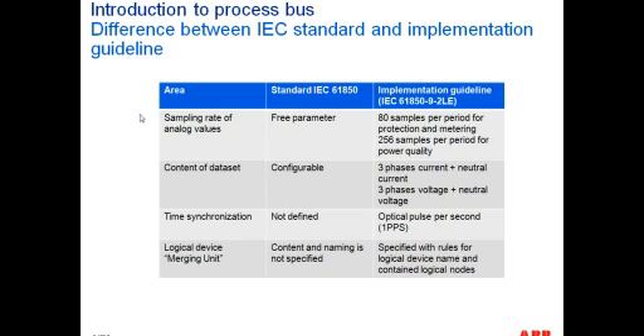So what are some of the things that the 61850 9-2 standard defines? Well, the first one, which is obviously essential if you're going to have devices from different manufacturers communicating via this network, is that you have to define a sampling rate. And what the 9-2 LE implementation guidelines define is that you must have 80 samples per cycle for protection applications, and then 256 samples per cycle for power quality type applications. What we've seen so far around the world is that the implementations are inside the protection and control domain. So what I've seen so far, in my experience, is 80 samples per cycle type systems.